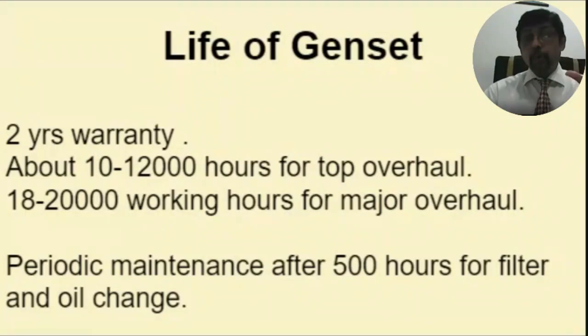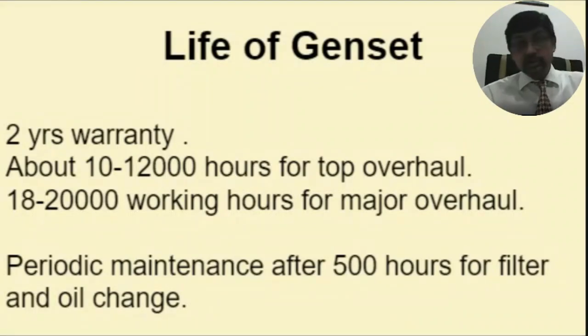But the top overhauling of the generator, the top overhauling means only the valves or probably injectors, which are taken care of from the engine side, I'm talking. So after 10 to 12,000 working hours of operation, the engine is opened only on the head. The head of the engine is opened, and the injectors or certain valves need polishing or replacement or probably repair, whatever can be done, they do. And this is required after 10 to 12,000.